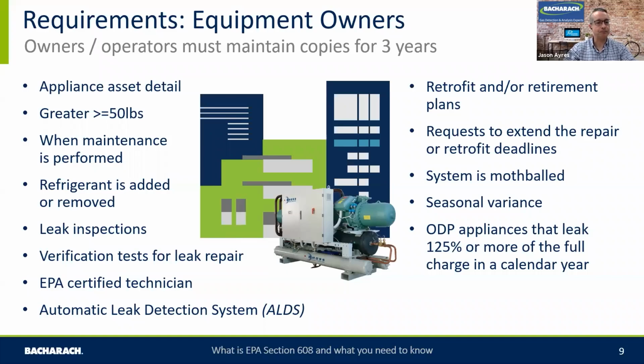If you have other equipment with carbon dioxide or ammonia, you may capture that, but there's no requirement to present that to the EPA. So as well as having the appliance and asset details, the other type of information is when any work is carried out on that equipment. And work could be adding refrigerant to the system. So that could be for a leak repair, a retrofit, or if refrigerant is being removed from the system, as you might be retiring that piece of equipment or doing a gas retrofit, you need to have records held for that type of process.